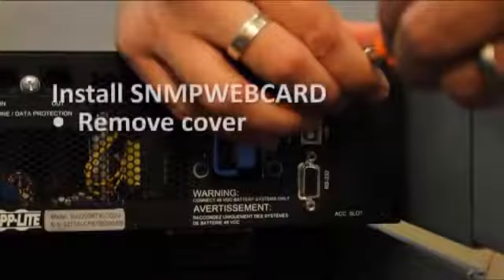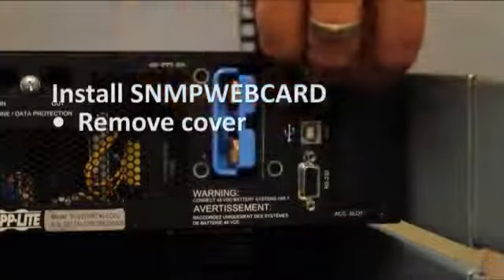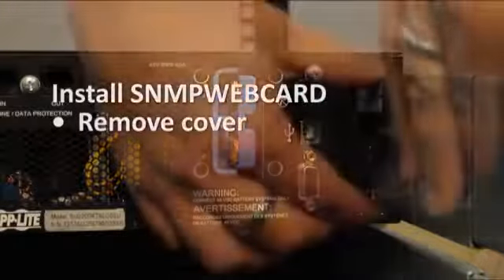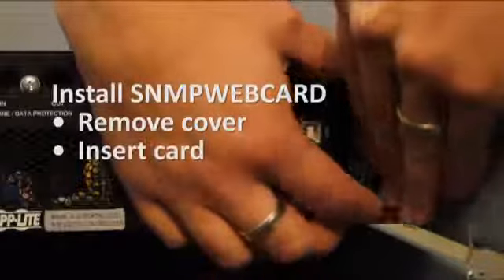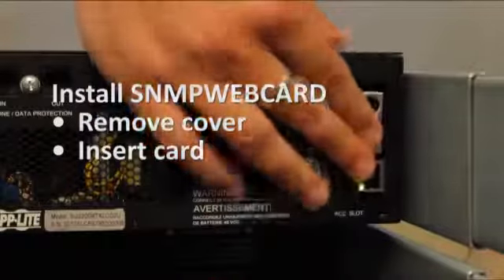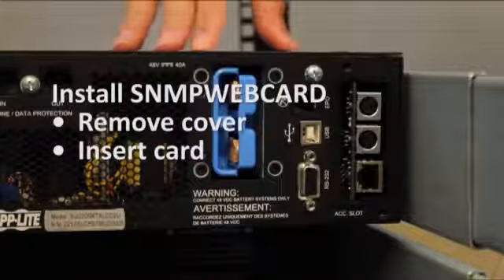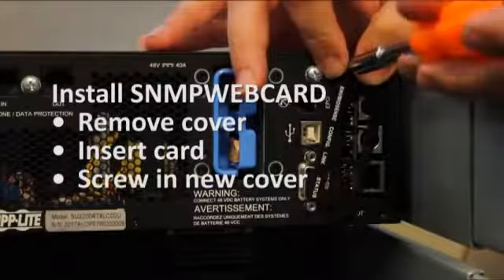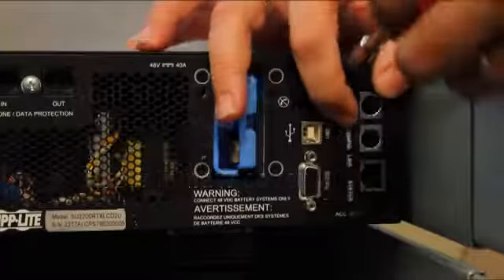Using a screwdriver, remove the card slot cover on the rear of the UPS system. Align the SNMP web card with the guides and push the card into the slot until the ports are nearly even with the rear surface of the UPS. Screw in a new cover that's included with the card.